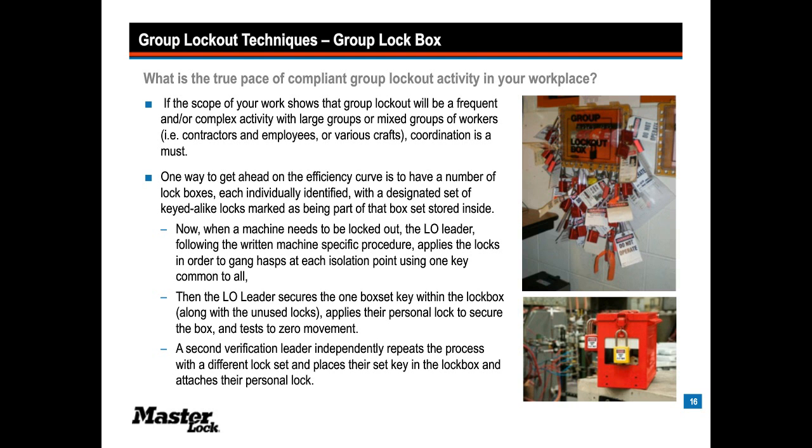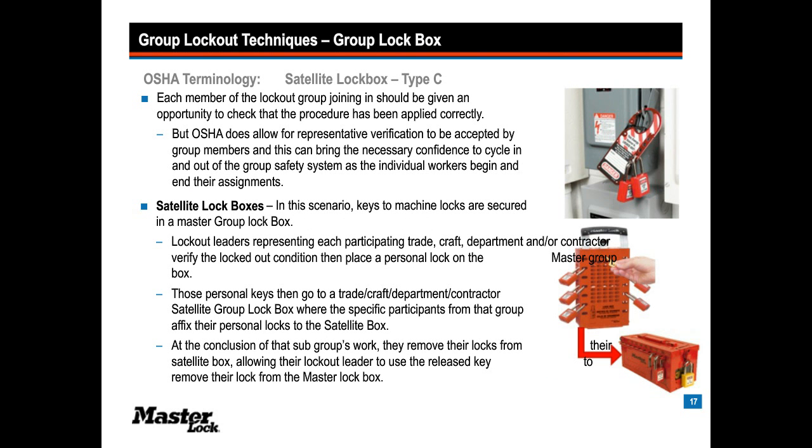Now, OSHA has another type of scenario. They call it a satellite lockbox. In this situation, each member of the lockout group should be given an opportunity to make sure the procedure has been correctly applied. But OSHA does allow for representative verification to be accepted by group members, and this can bring the confidence to lock in and lock out of the lockbox knowing that the machine is fully controlled.